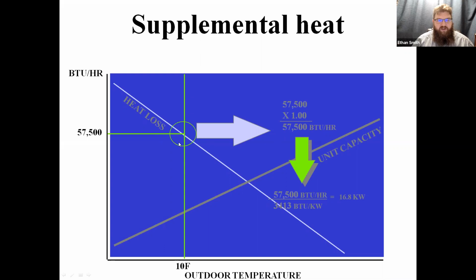So at 10 degrees outdoor temperature, my house requires 57,500 BTUs of heat. Okay. So if I were to shut my heat pump off at that capacity balance point and provide all the heat I needed, that 57,500 BTUs, I would need 16.8 kilowatts of heat to make 57,500 BTUs per hour. We can calculate that by simply taking the BTUs that we require and dividing by 3.413. That number should be familiar because that's 3.413 BTUs per watt, multiplied by 1,000 to make it kilowatts. And that will tell us how many kW of electric heat we need in order to generate 57,500 BTUs per hour of heating with auxiliary electric heat. Okay, so this helps us size.